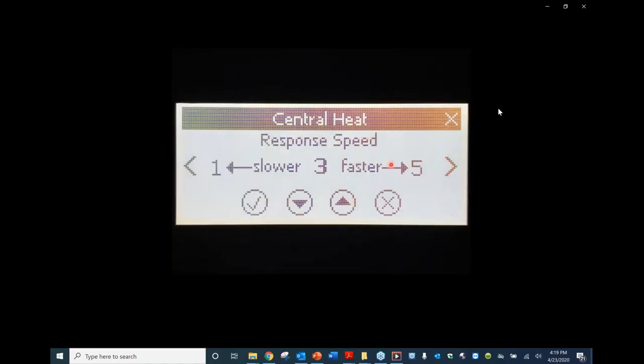Next menu in here is going to be our response time. And this is going to be how quickly the boiler starts to modulate. We turn it down to 1, the boiler's not going to modulate very quickly. It's staying on fire. It's not going to react to the system very, very quick. And move it all the way up to 5, it's going to react really, really quickly. We may wind up overshooting our set points. 3 seems to be the best setting for it, and that is where it is left at the factory. You can play with it as you need or as you feel. But 3 is primarily the best setting for it.